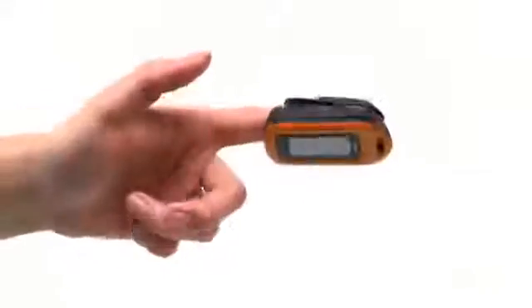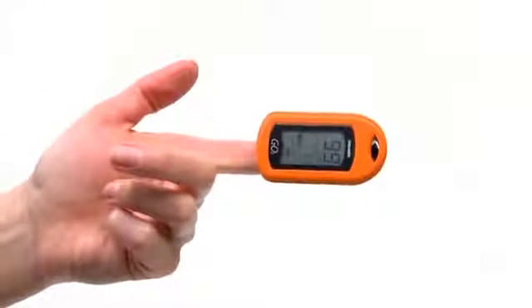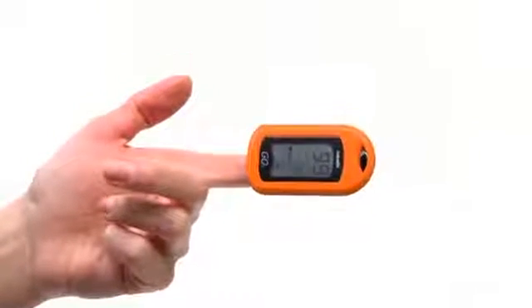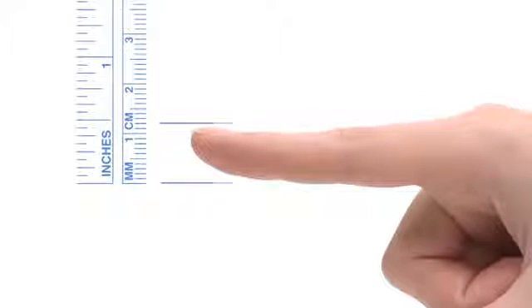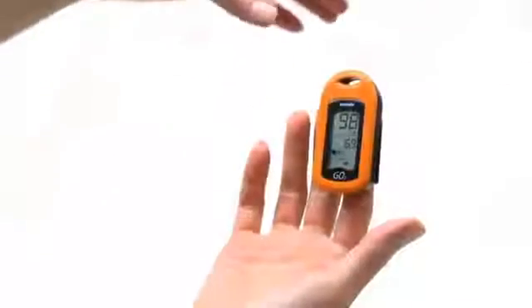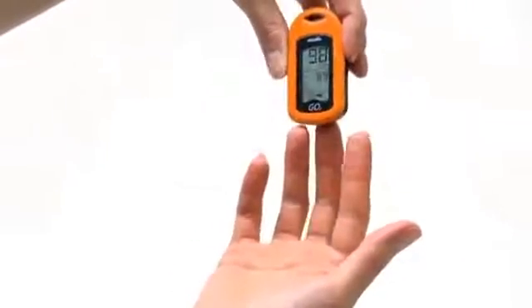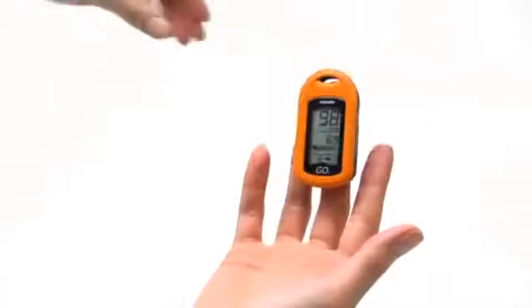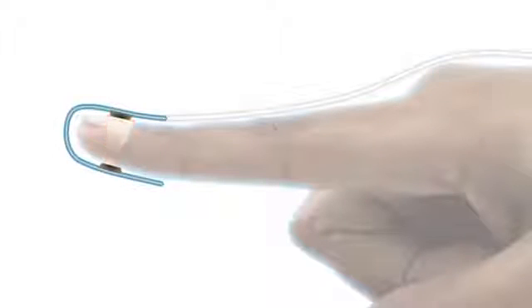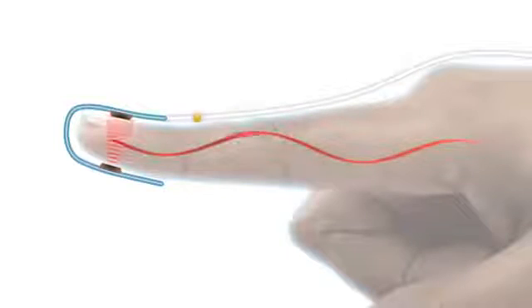The GO² oximeter is used on the index finger for finger thicknesses between 1/3 to 1 inch thick, or 0.8 and 2.5 centimeters thick, measured from the top of the finger at the middle of the nail to the pad of the finger. The GO² oximeter may be used on other fingers if directed by your clinician. Changes in the light wave spectrum through the finger during pulsation of blood generate a measure of blood oxygenation and pulse rate sent to the pulse oximeter.